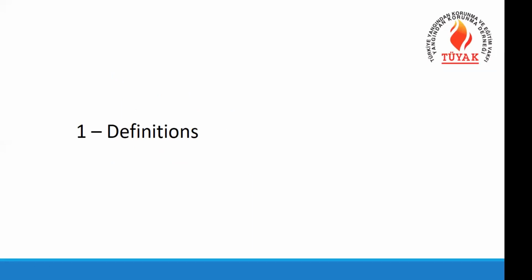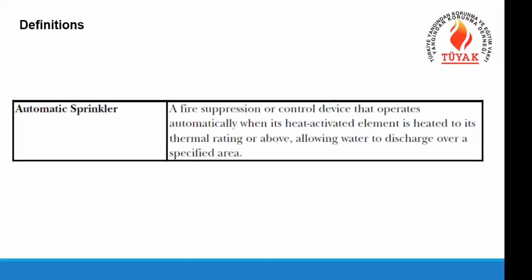Let's talk a little bit about the standard definitions of fire protection systems. Sometimes we see that the basic and most preferred fire protection system in industry is the automatic sprinkler. This is a fire suppression and control device that operates automatically when it is heat activated. So we need some heat to activate a sprinkler, and it has an element that, upon heating up to some degree, activates, and water discharges over the specified area to control the fire. This is called the automatic sprinkler. You don't need any extra detection device because it is already a detection device. It has a heat-activated thermal element.